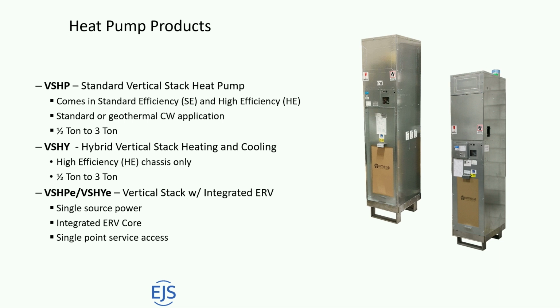Bathroom exhaust has to go out, so in lieu of centralizing it up the middle of the building, we can free up shaft space, bring this bathroom exhaust through the heat pump, through the exterior wall, and bring outside air through the heat exchanger on the other side, reclaiming some of that heat from the bathroom. We can bring outside air up to 150 CFM pretty much 24/7, right? And we have special freeze protection sequences so we don't freeze coils, and we don't bring in cold drafts into the space.